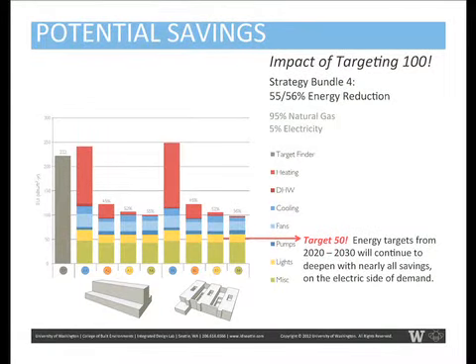So we have these basically VAV options that are heavily VAV and plant systems that are very traditional. But what really surprised us, and thank you owners, is that option 2 and 3 performed really pretty well. We couldn't quite hit 60%, but we could hit 50%. And so we all felt a little embarrassed, like, oh gosh.